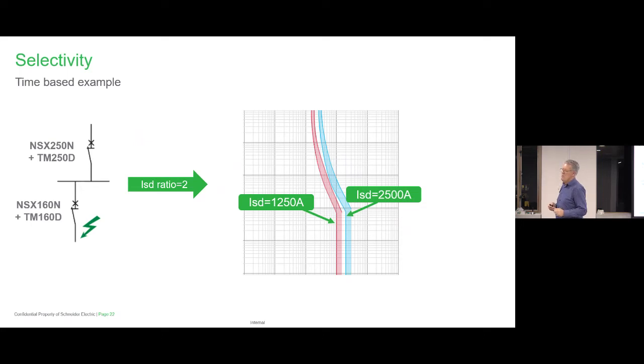But let's say you're a contractor and you're on a brownfield site, and you are installing a panel. For argument's sake, you're installing a new MCC panel from Schneider, and you're being supplied by an ABB upstream circuit breaker. What would you do in that case? Well, I would talk to the electrical engineer who says that they use a product called PowerCAD, and it has multiple brands that you can compare for discrimination, or what we're now calling selectivity.